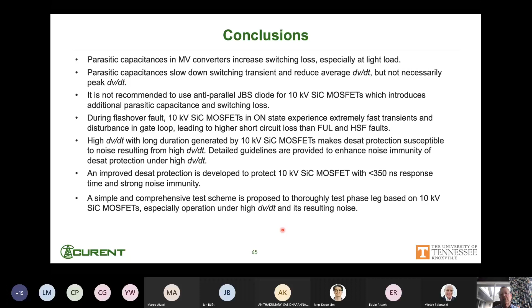Flashover fault, you can experience very fast transients and disturbances, and so those faults are actually worse than fault under load and hard switch faults. And the high dv/dt has a long duration with these high voltage devices, which makes them more susceptible to noise. So you really need to spend a lot of effort on your desat protection to make sure it's more immune to noise. And then we talked in general about some of the things you need to consider when using these very high voltage devices.